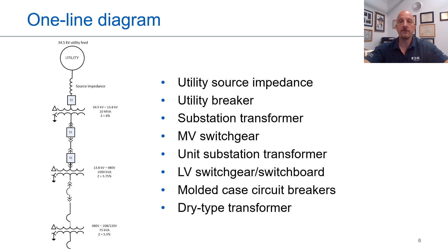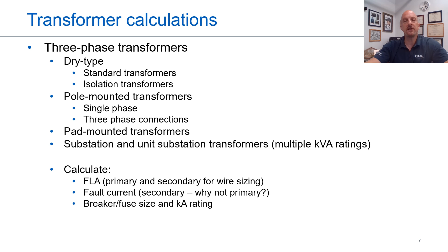Now what we're going to do is we're actually going to go through and calculate full load amps on the primary and secondary of a transformer, the fault current on the secondary, and also the breaker or fuse size and the KA rating of those breakers. We're going to talk about how that comes into play here. Now, I'm going to actually take you for a walk and show you a couple of these transformers so you can physically see what they look like, because they're not just squiggly lines on a piece of paper. They're actually physical devices. And I'll show you the difference between the liquid-filled ones and the dry types and the pole-mounted ones and the things you're going to have in your one-line diagrams that won't necessarily correspond to something physical you've seen before. And I think that's really important to see how that all comes together.